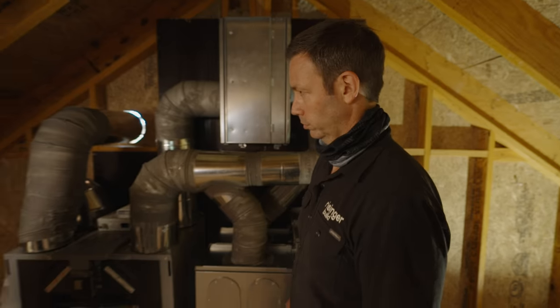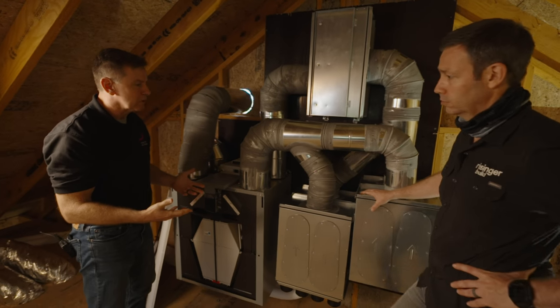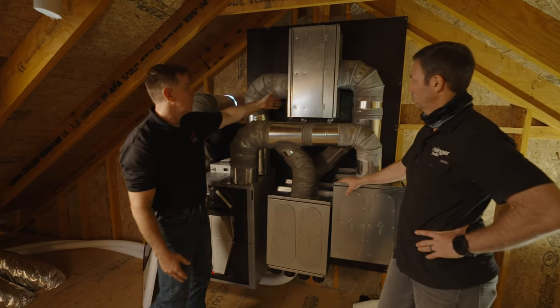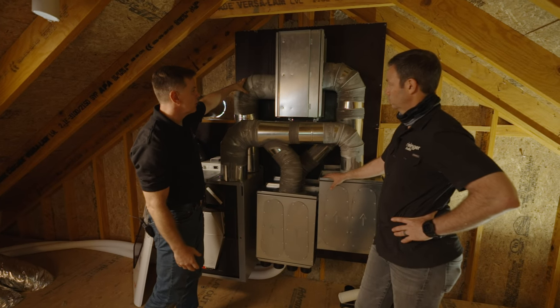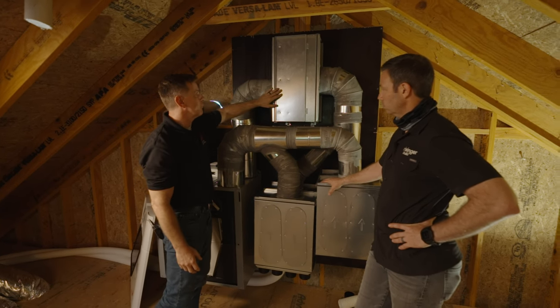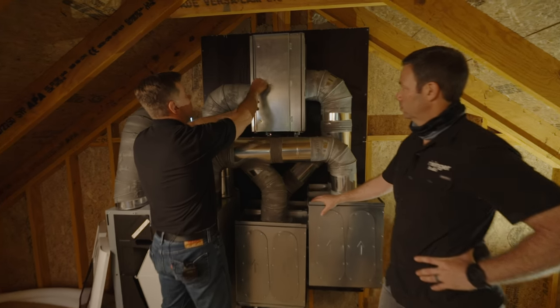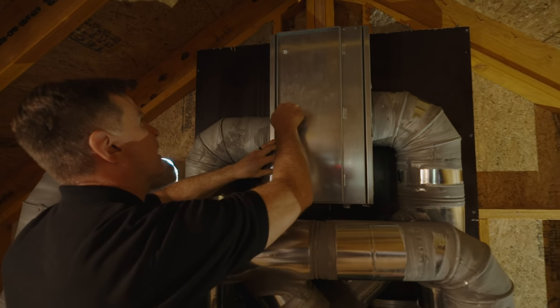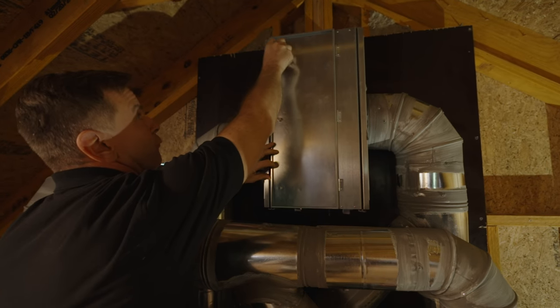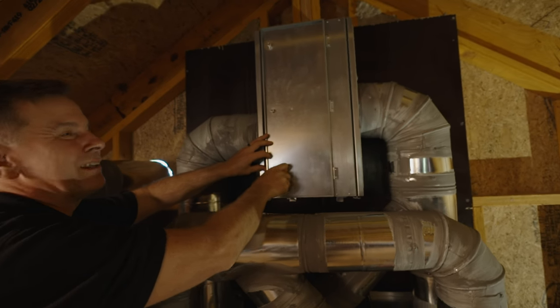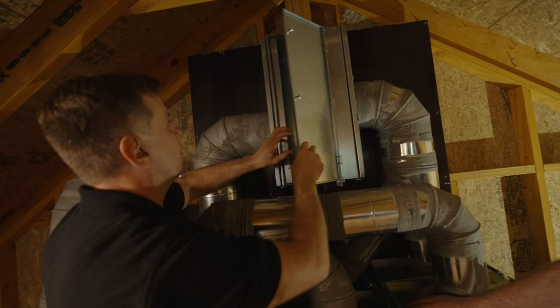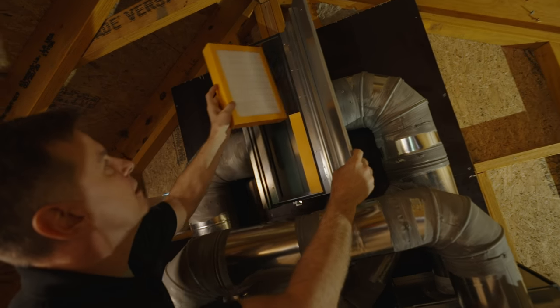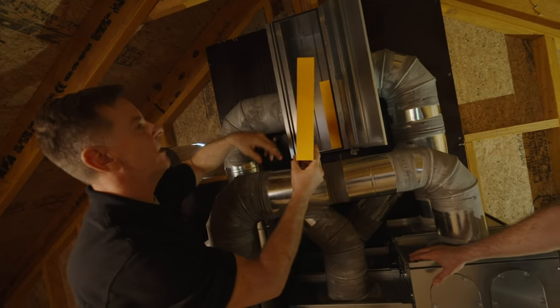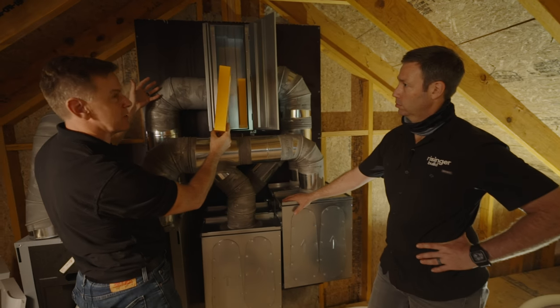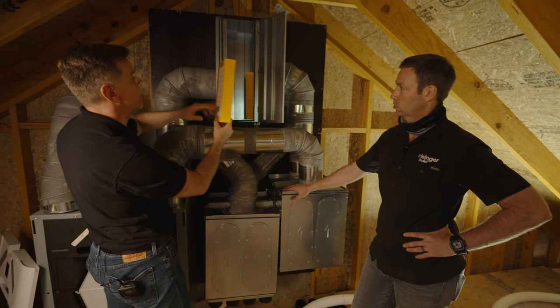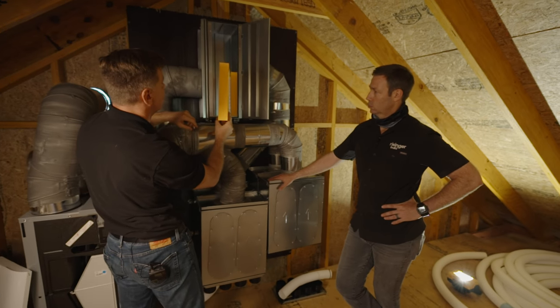That's right. In your case, and we can do this as an option, up here our supply air coming out, before it gets distributed to the house, is going to go through an additional filter casing. If we open this up, we'll see inside we've got an upgraded filter. This is actually a MERV 15 filter, getting basically into your hospital outpatient type category of filtration. That's really high filtration. And as you can see, we've got more surface area, so we're not going to add a lot of static pressure to the system, and we've got a bigger, thicker filter that's going to give you a longer lifespan.